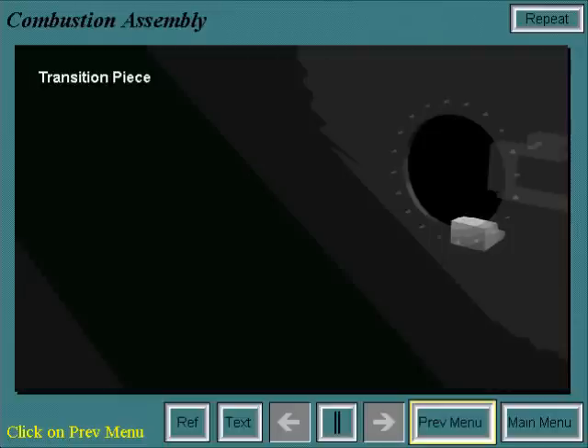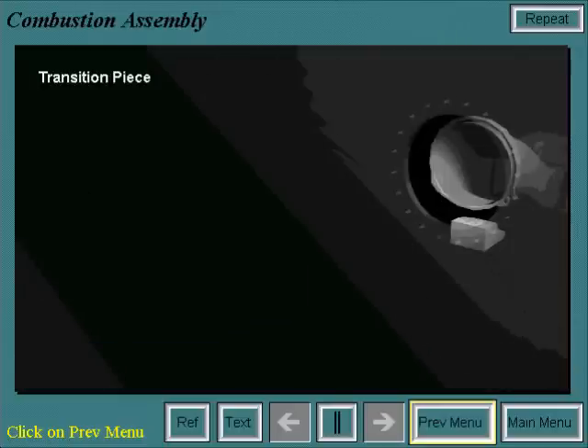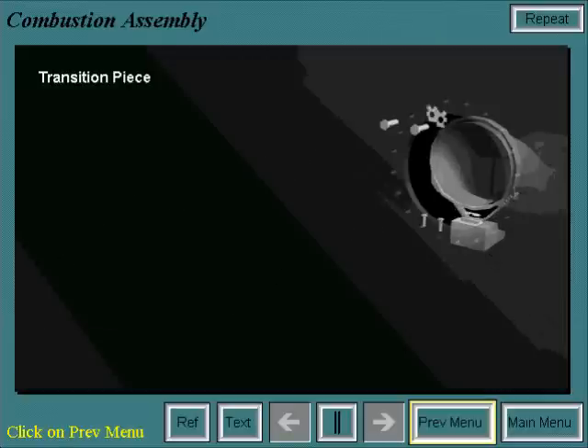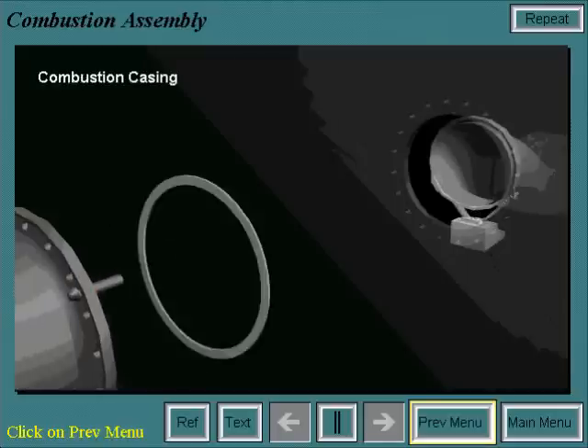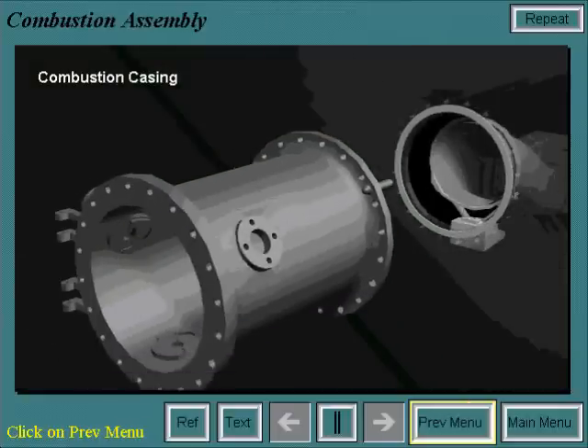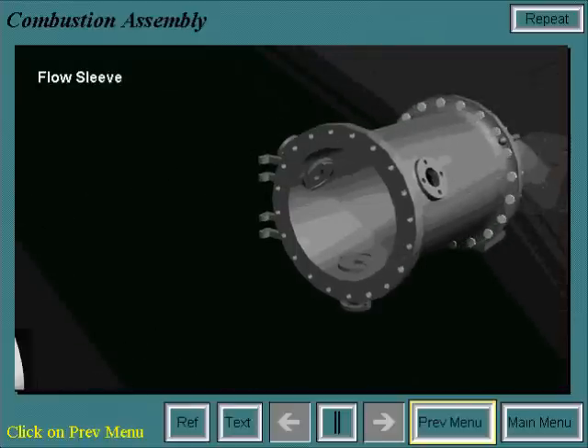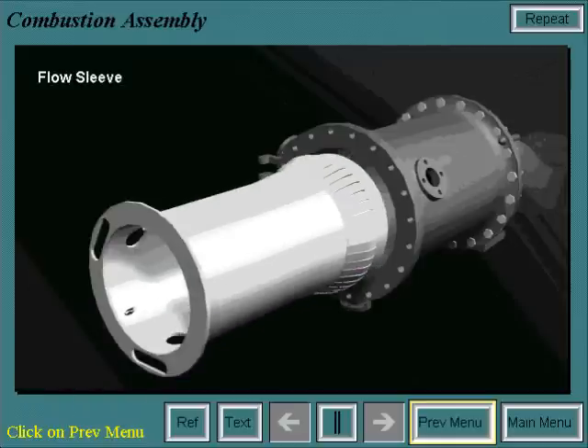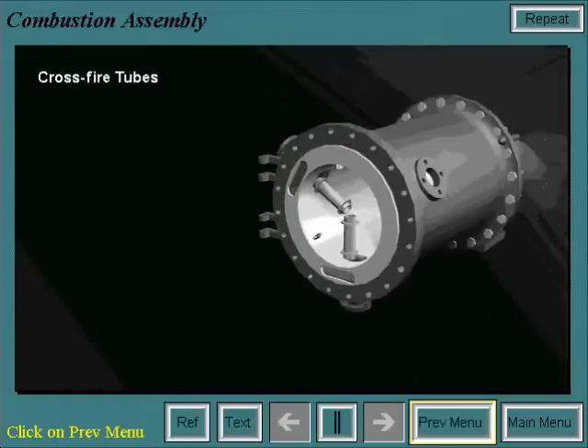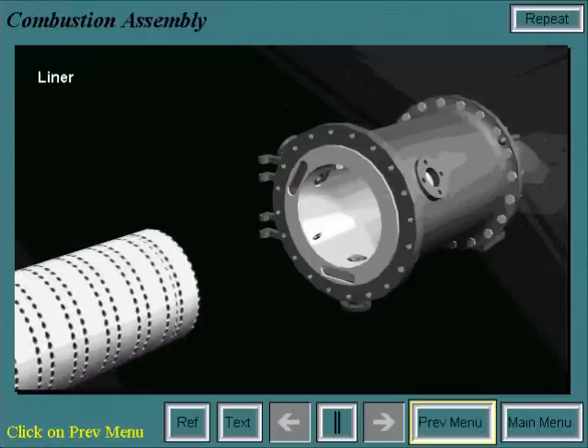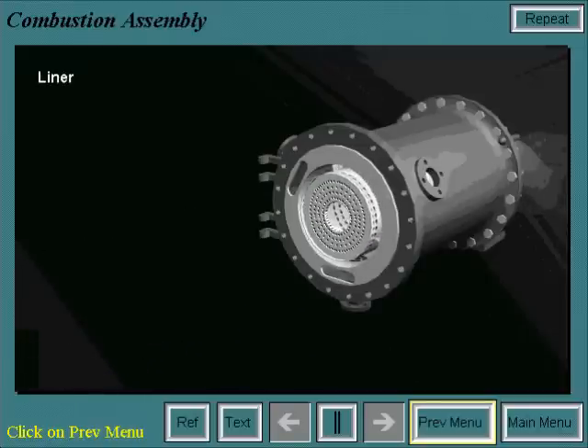The assembly of the combustion system begins with the transition piece bolted to the first stage nozzle on its aft end and supported by the bullhorn bracket on its forward end. Next, the combustion casing is bolted onto the combustion wrapper. Then the flow sleeve slides into the casing. The crossfire tubes are then installed, but pushed out of the way so that the liner may be installed. Once it is, the crossfire tubes are put into the crossfire tube collars in the liner.